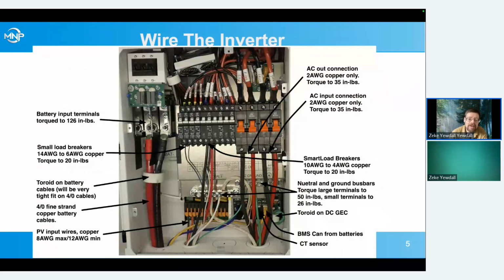Here's what it looks like all wired up. We've got our main battery cables. We really want to use 4-aught wire for this. We've had a lot of issues with shutdowns and problems under surge loads with people using 2-aught cables. This inverter really wants full voltage, and it can pull over 400 amps under surge loads. So 4-aught battery cables, don't undersize those. We've got our toroid on the battery cables that helps smooth out ripple and reduce noise.